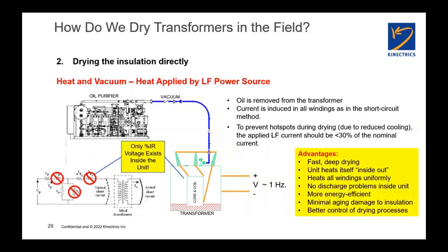With low frequency heating, I'm generating the heat right where I want it, which is in the windings of the transformer. So the advantages are that we get very fast, very deep drying of the bulk of the paper, not just the surface. The transformer heats itself from the inside out. All windings are heated uniformly, and it's very energy efficient. And most importantly, because I have good control of this process, there is no damage to the paper insulation. I'm not going to over dry it, which can lead to loss of degree of polymerization, believe it or not.